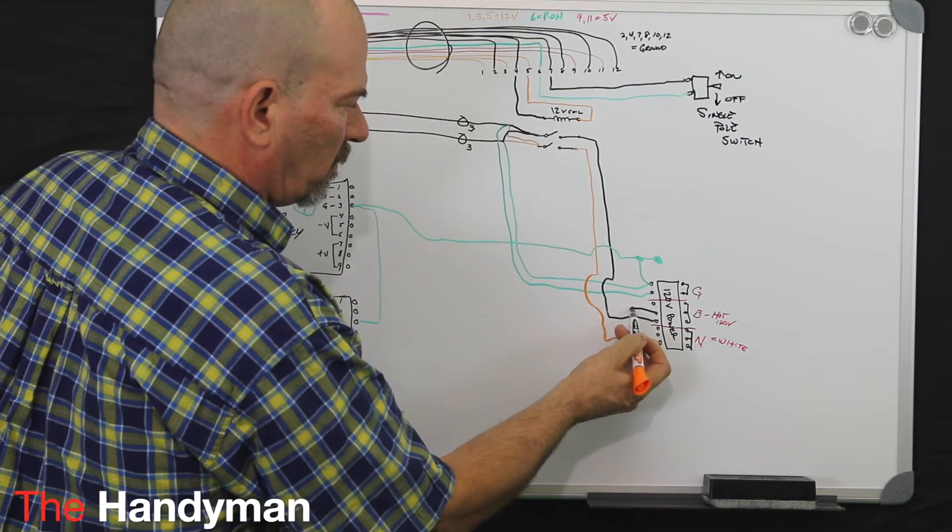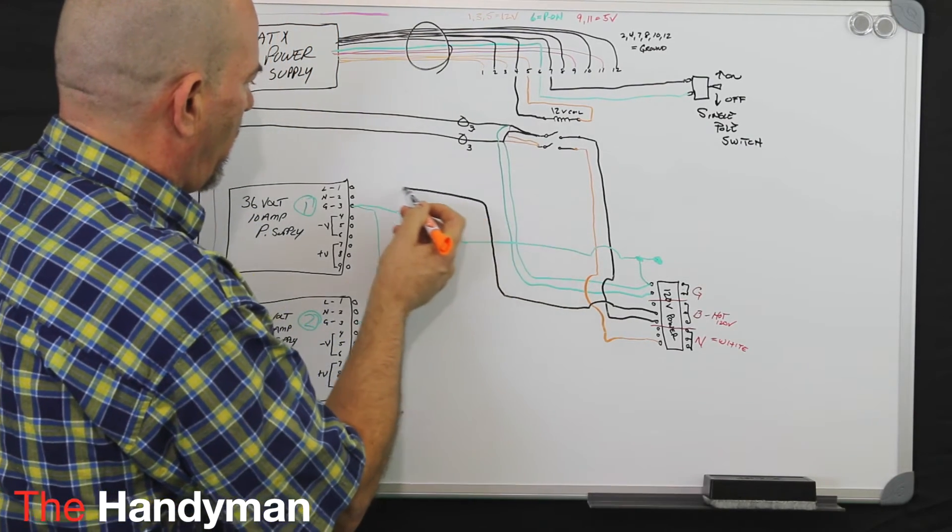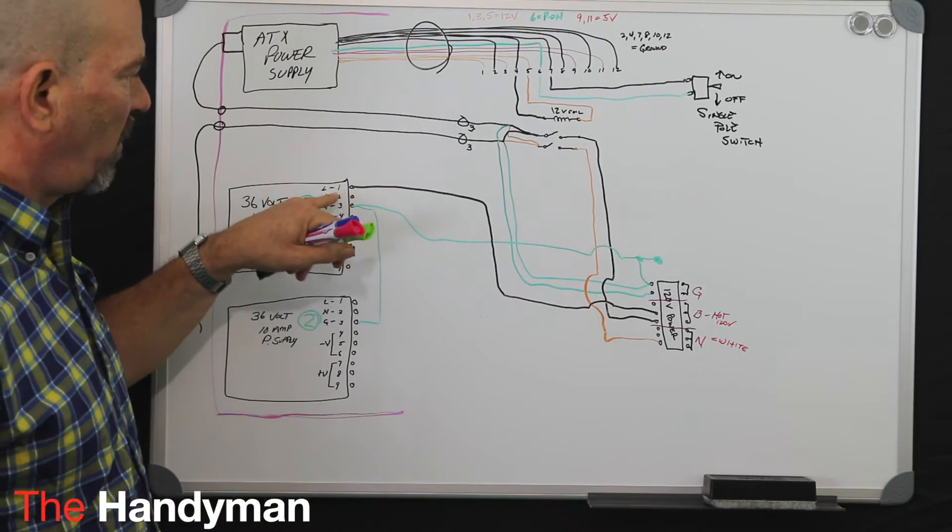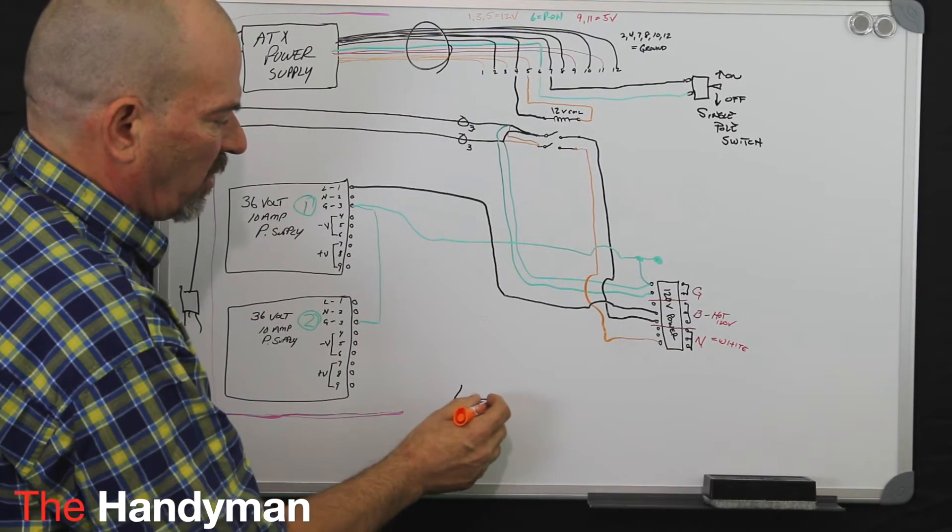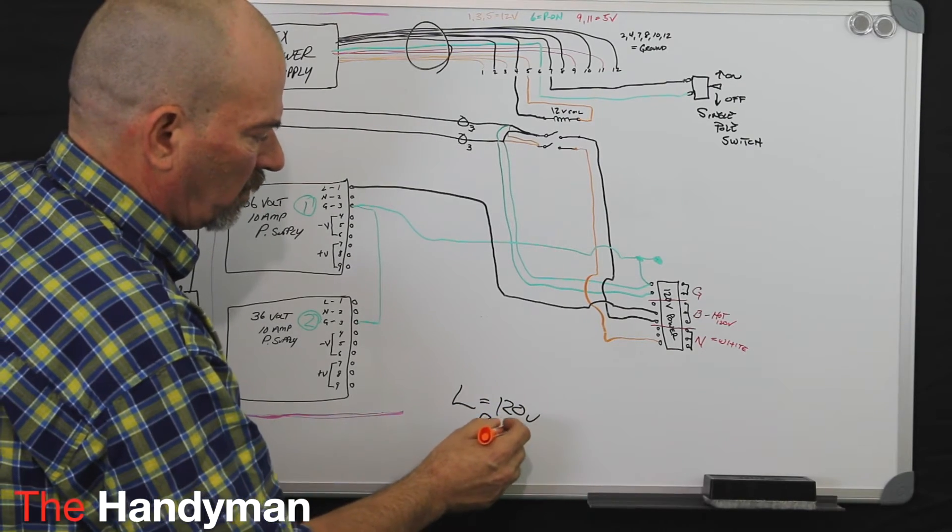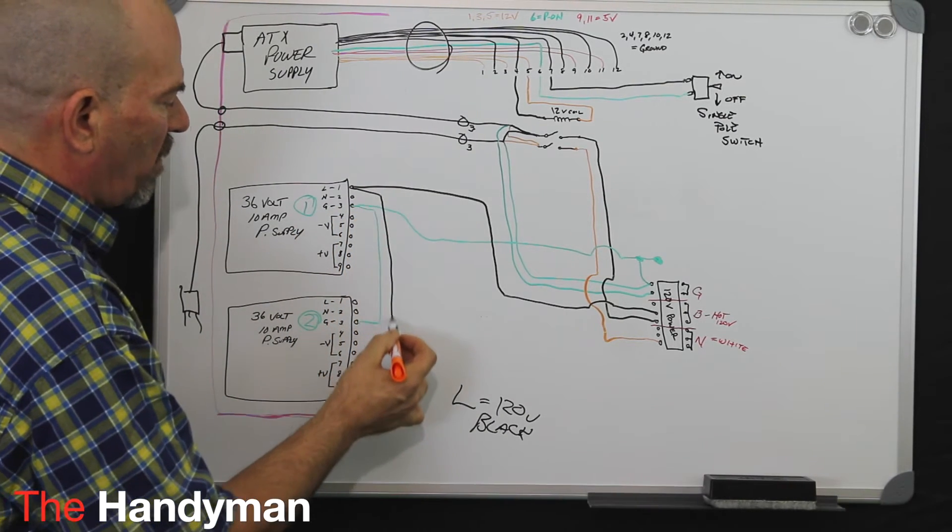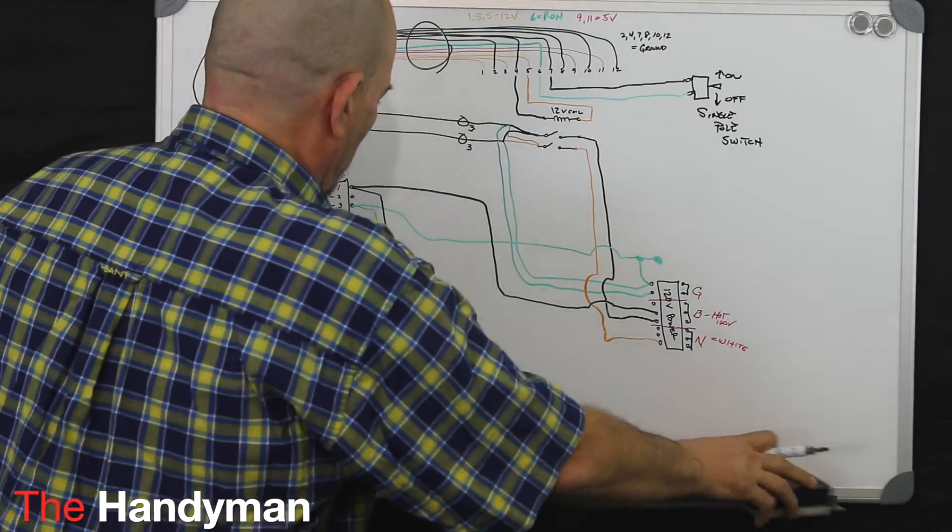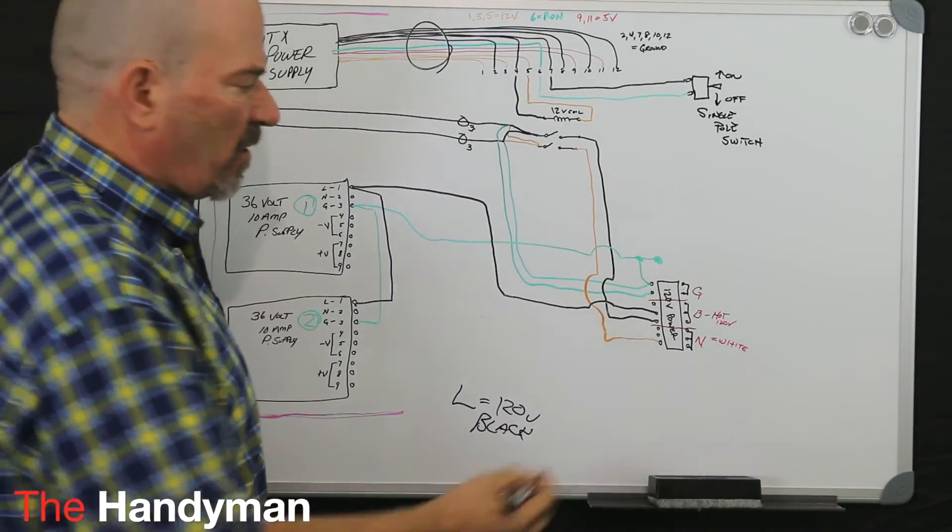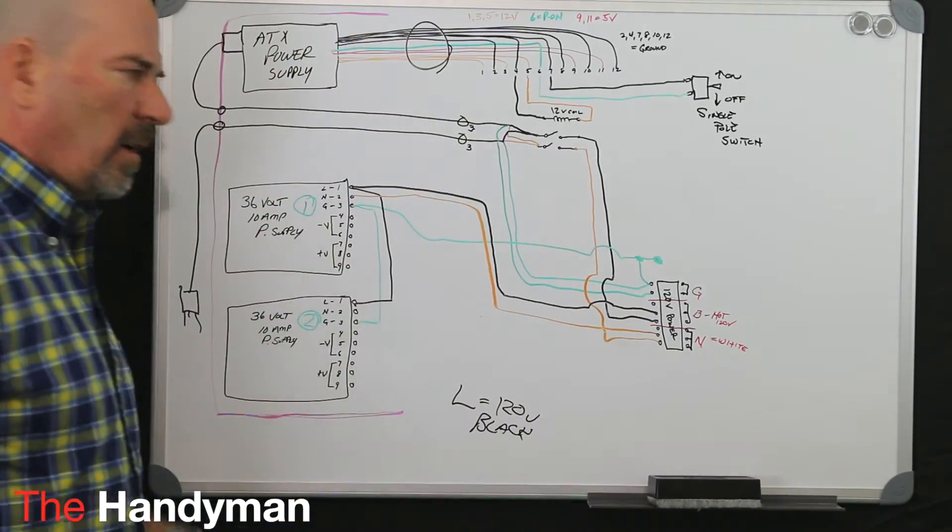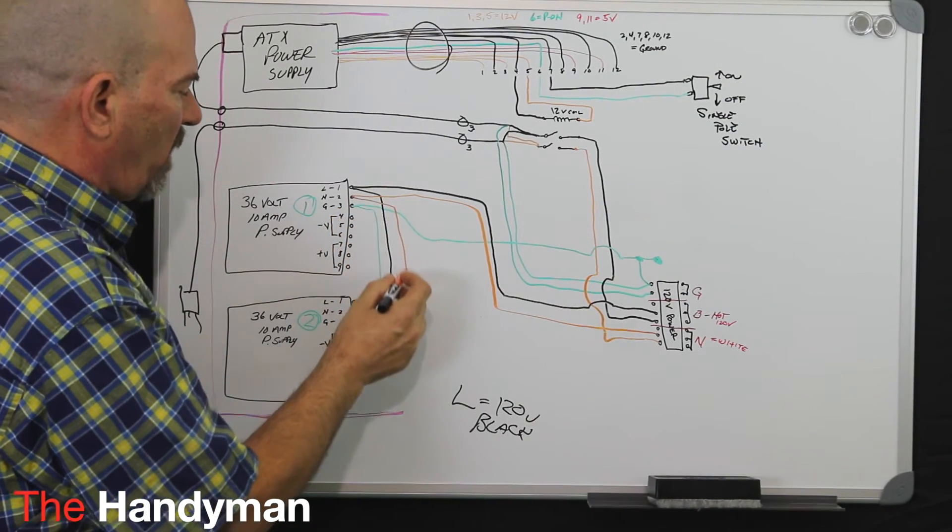So next we'll take one of the blacks from that screw, bring that up, and on my power supplies, which yours should be too, the first screw is your line represented with an L, which is your 120 volt side or your black. Then you'll take and make a jumper off that to come down to your other power supply. I went a little far there, and you will put that under your power supply. Then you'll come off your neutral and you'll go under terminal number two, which is marked with an N. Then you'll make a jumper and the same thing, you'll come down here into there.